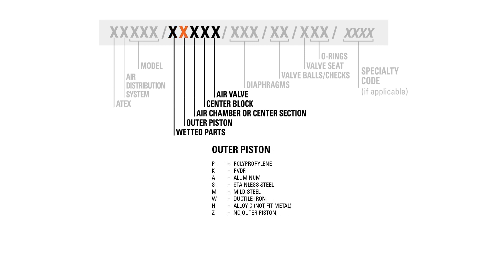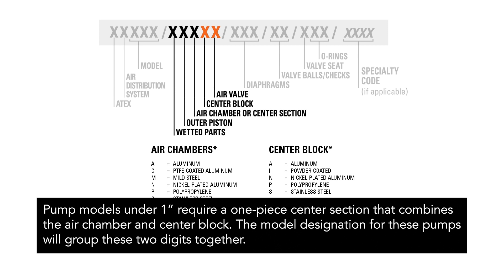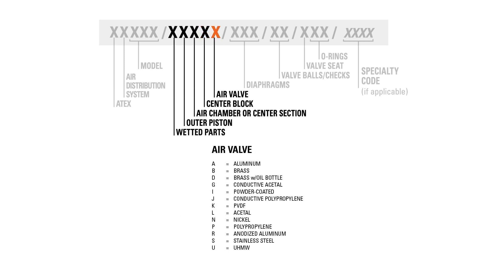The second digit of this section denotes the outer piston option for the pump. In most cases, this will match the wetted parts material of construction. The pump may also not have an outer piston if the diaphragm is integral piston, such as chemfuse or purefuse diaphragms. The third digit denotes the material for the air chamber and the fourth digit denotes the material of the center block. Pump models under one inch require a one-piece center section combining the air chamber and center block, so the model designation groups these two digits together. The final digit in this section denotes the material of the air valve, and some air valve materials are specific to the air distribution system used.